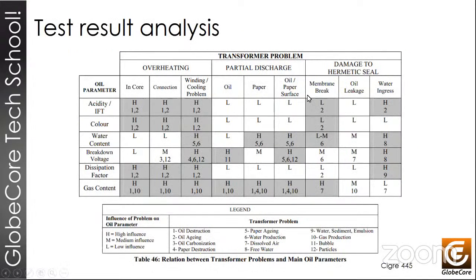And this is another very interesting table that we can find in the CIGRE 445 document, and it's a very well done matrix. We do our oil analysis or our tests many times, but we might not be very clear on what is causing the malfunction and how it's related to the information that we analyze or the information that we're going to get from this particular test. It shows us 3 different problems: overheating, partial discharges, and leakage or seal failures in the transformer. These will be the 3 main groups of transformer problems. Each of them is divided into 3 subcategories. For example, overheating in the core, connections or windings and cooling systems.